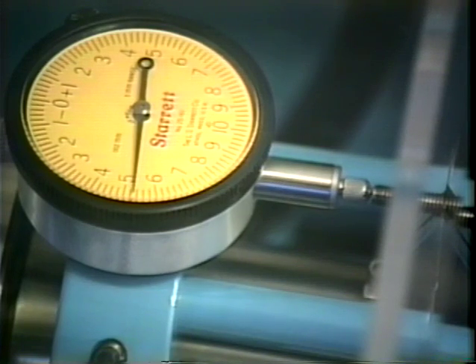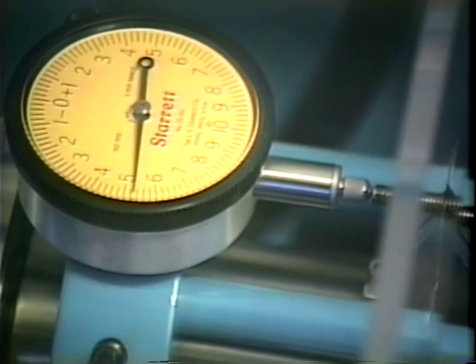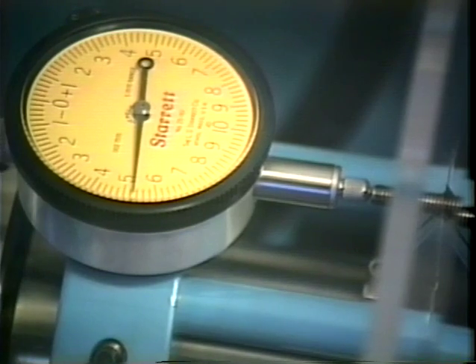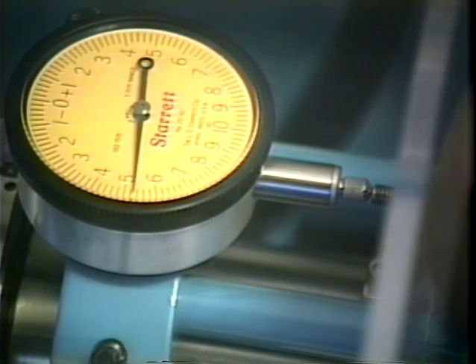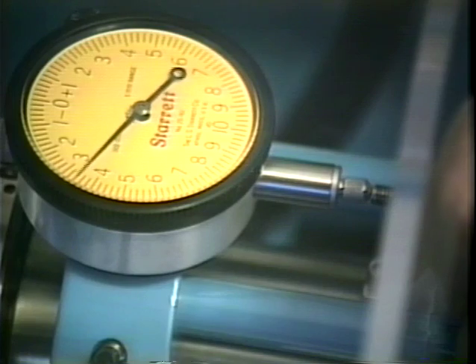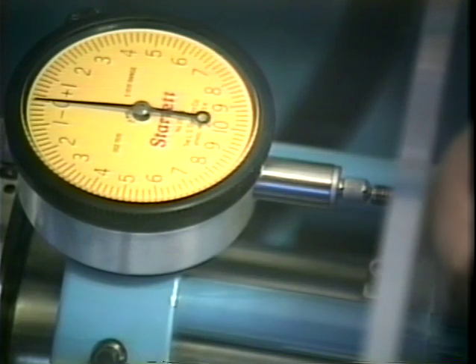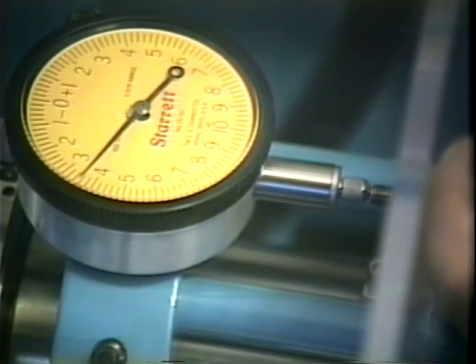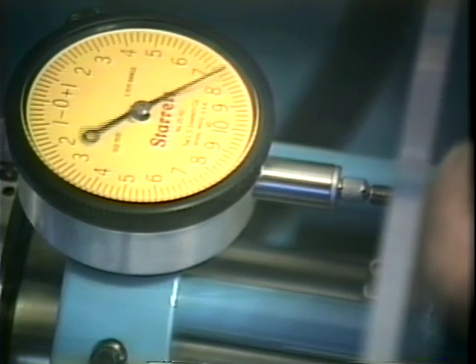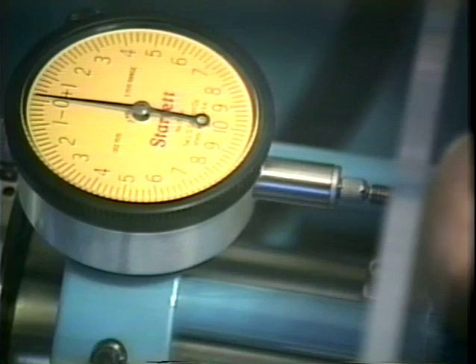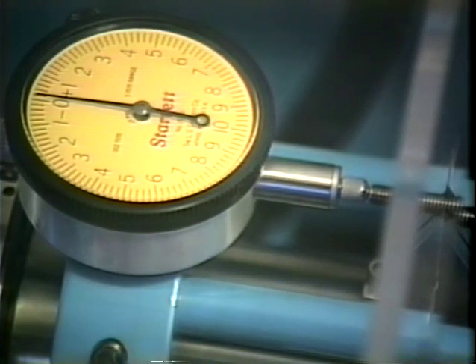The calibration of the dial indicator is shown in greater detail here. We're rotating the diamond plate, bringing it closer to the glass slide with the micrometer. There we have touch off. Now we'll use the calibration screw to calibrate the indicator. There we have activation on the dial indicator pointer to 0, plus one revolution to 0, two revolutions to 0. The dial indicator is calibrated at that point.